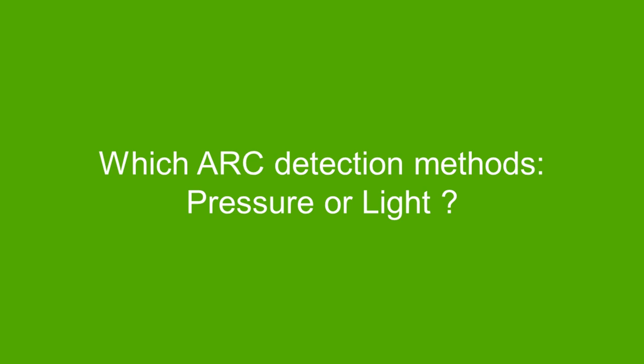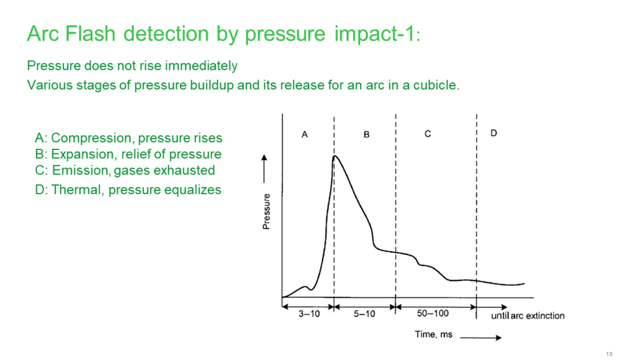Now we want to apply the arc flash system. What method should we use? We can use pressure sensors or light sensors. Looking at the pressure sensor first: pressure does not rise instantaneously. Research done in one cubicle identified four stages: first, compression and pressure rise taking 3 to 10 milliseconds; then when the pressure relief opens in the switchgear, pressure drops — stage B, another 5 to 10 milliseconds; then emissions and gas drop — pressure starts to decrease in area C; and finally, pressure equalization in part D.